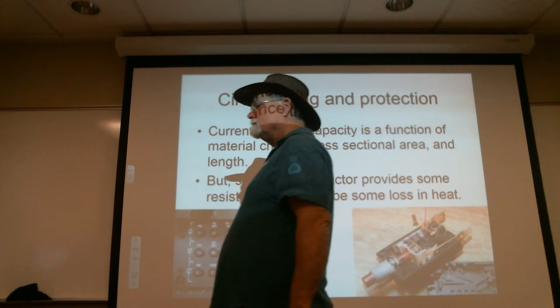We use charts based on a certain amount of voltage drop. Within the wire gauge system, you can find calculators online, but there are charts showing voltage drop for any wire using standard copper, multi-stranded wiring. There's a bit more voltage drop with multi-stranded wiring than single solid core, however solid core isn't flexible enough for use in an airplane.